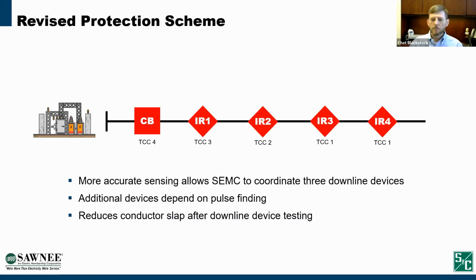So this is what our protection scheme looks like now. As I mentioned, we can coordinate 3 interrupters in series. If we have a fourth, if it's a really long feeder and we install a fourth interrupter, it doesn't coordinate with the third interrupter, but relies on pulse finding. And we don't have many feeders where they're long enough to justify 4 interrupters, but we frequently get this configuration when we're backfeeding feeders. So we've got one feeder backfed by another all the way back to the station. We may have 6 or 7 interrupters in series where the last several will rely on pulse finding.